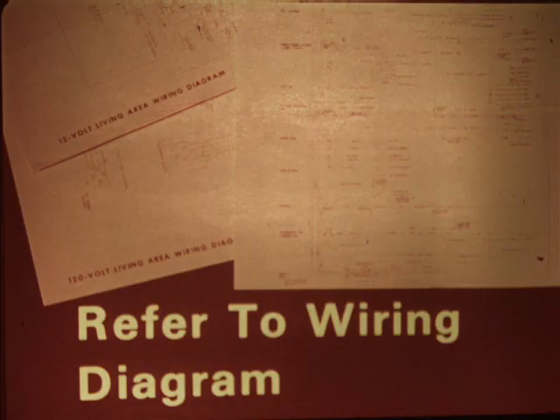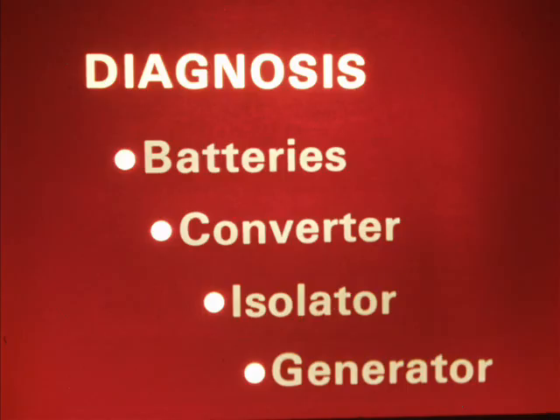If you want to charge the automotive battery from the power converter, you can do it by connecting both battery wires at one terminal on the front mag switch. So that's the operation of the charging systems. When you approach diagnosis, be sure to refer to the wiring diagram to refresh your memory and locate test points. Now let's discuss diagnosis of the system in this order: the batteries, the power converter, the dual diode isolator, and the generator.